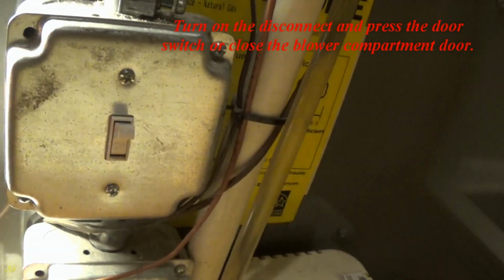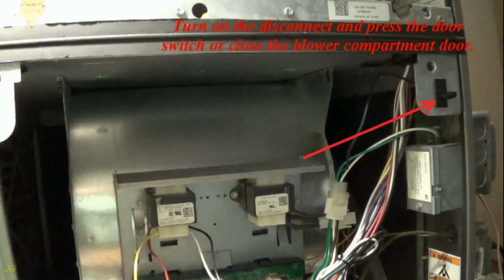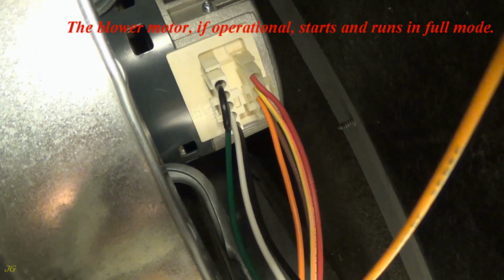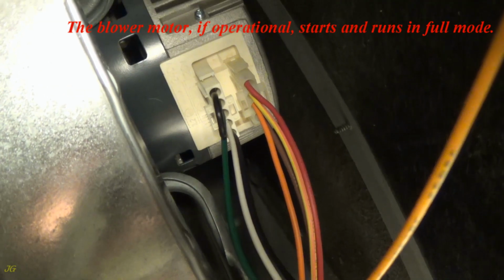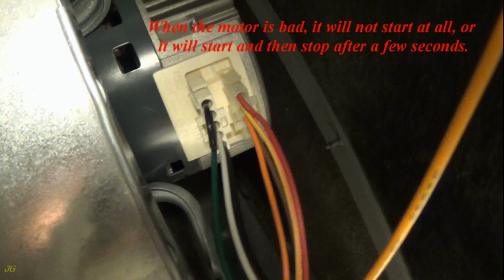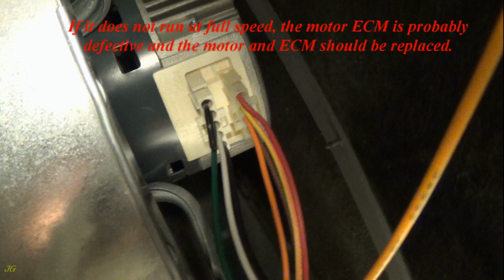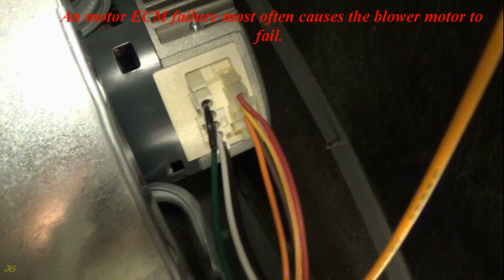Turn on the disconnect and press the door switch or close the blower compartment door. The blower motor, if operational, starts and runs in full mode. When the motor is bad, it will not start at all, or it will start and then stop after a few seconds. If it does not run at full speed, the motor ECM is probably defective and the motor and ECM should be replaced. And motor ECM failure most often causes the blower motor to fail.